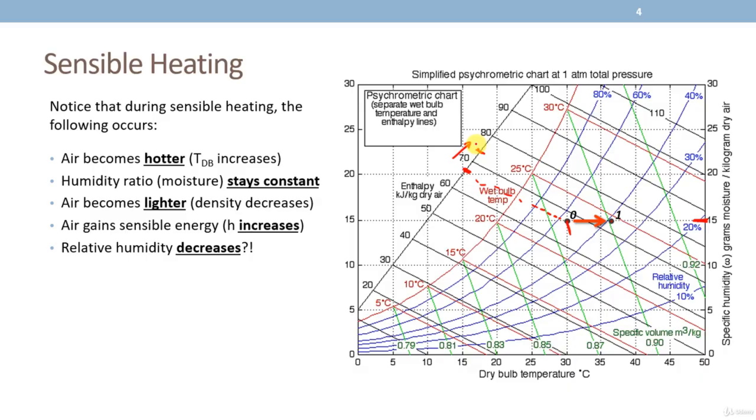And lastly, the one that is not so obvious, whenever we heat up the air, relative humidity will decrease. The easiest way to explain this is using this illustration again. As I mentioned before, the dry bulb temperature is as good as the container capacity, the amount of water inside the container is as good as your humidity ratio, and percentage filled is equal to RH.